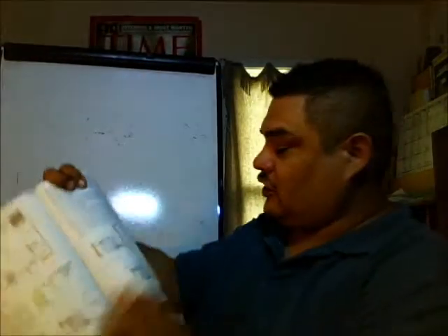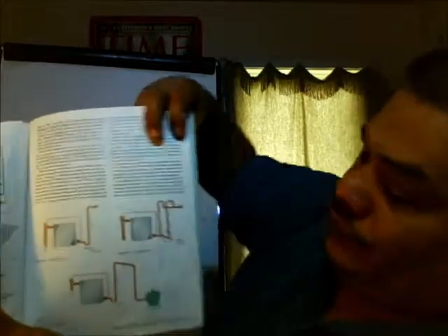Number 8, traps at the bottom of the suction line risers help to, this is in your book, create turbulence, which helps entrain oil and carry it to the top of the riser. I'm going to be honest, I don't know too much about that. I'll show you a picture here. This is what it's talking about. It's right here, the little traps.